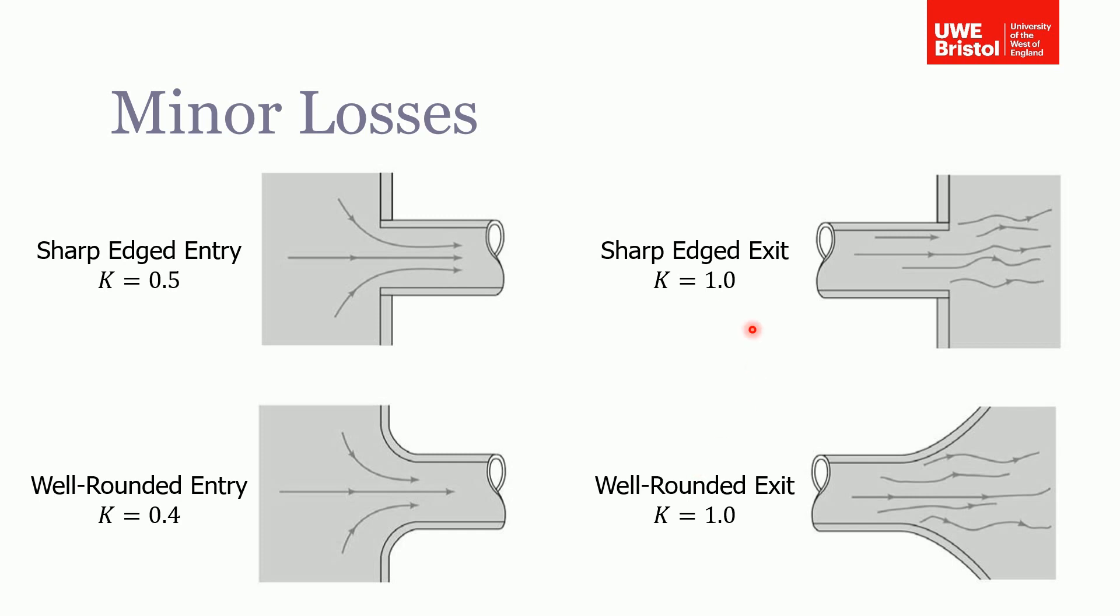So depending on what is in your system, you just need to find the corresponding pressure loss coefficient to plug into the general formula, and you also need to know the velocity in the pipe to work out the actual pressure loss for that component.